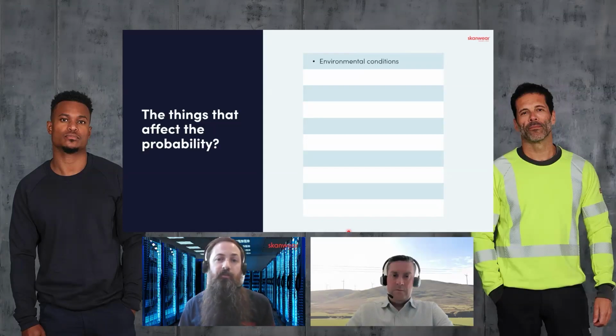So, environmental conditions. Typically we might have a plan around how we're going to make the system safe, but environmental conditions can often be out of our control. Like we've said, if it's outdoor, things like weather, other people, changing conditions. It might even be things like humidity. When we're talking about arc flash, there's a direct link between humidity levels and PD, which leads to tracking, which often leads to flashover. So it's about considering what's going on in the area, whether there's adjacent works, or whether you might be close to things like crop fields where they're cutting down crops, which can introduce debris into systems, which then results in flashover.